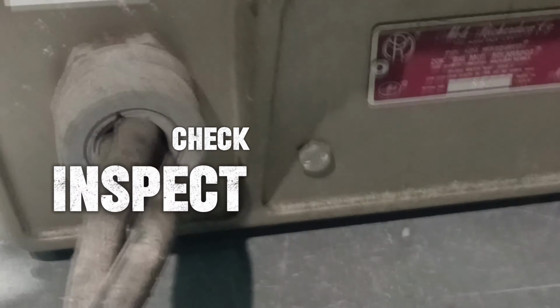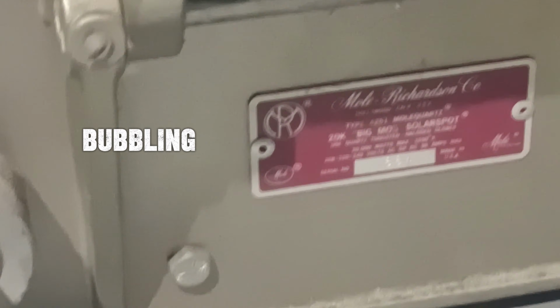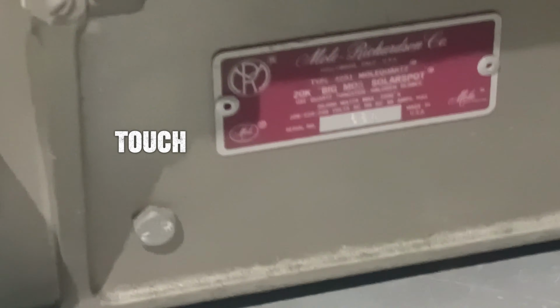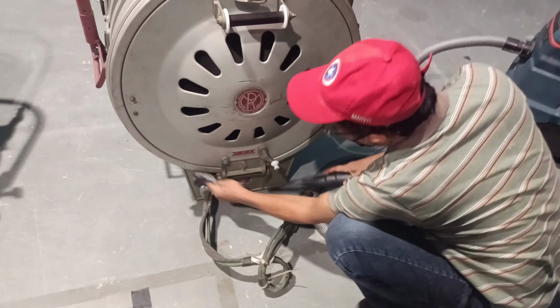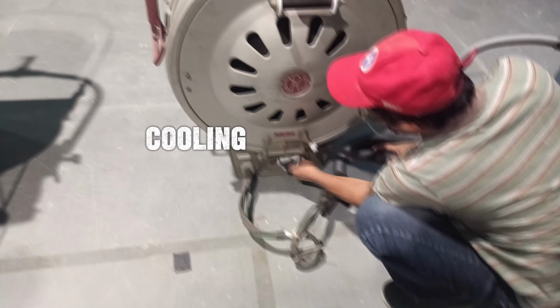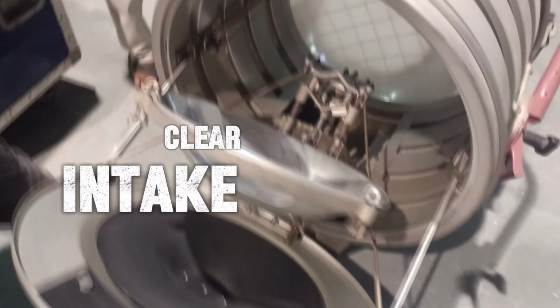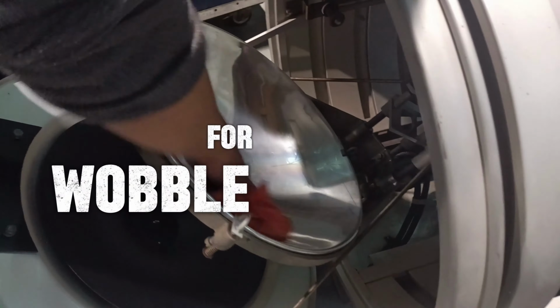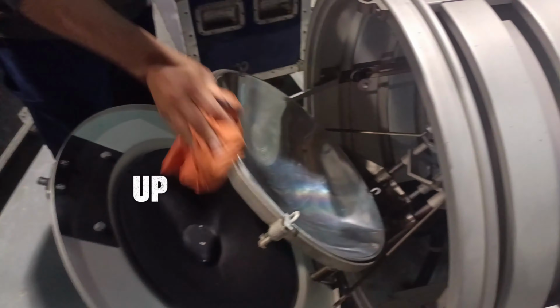Housing check: inspect for corrosion, paint bubbling, or impact damage. Touch up or replace panels as needed. Ventilation and cooling system, airflow pathways: use compressed air to clear intake and exhaust vents. Fan assembly: inspect for wobble, noise, or dust buildup.